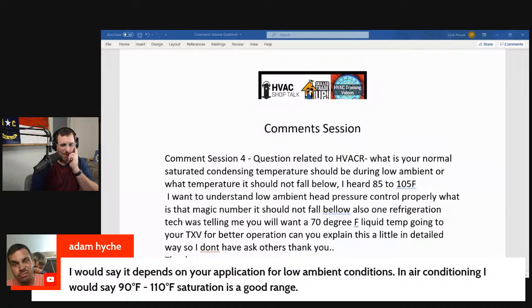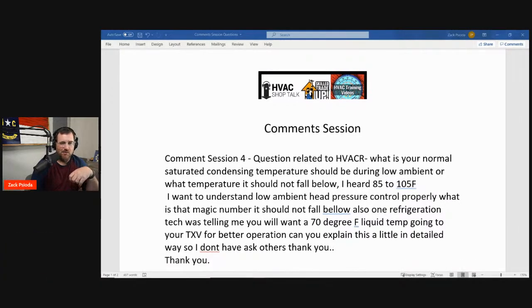I would say it depends on your application. For low ambient conditions and air conditioning, I would say 90 degrees to 110 saturation is a good range. That would put you right in that area we were talking about. So 70 degrees with 20 degrees over ambient will put you at 90 degrees. Maybe that's a good place to start. Like I said, I come from air conditioning, so I'm going to give you air conditioning answers. Okay. So that's where we're at on that one. That's probably the best I can do on that. Hopefully that helps a little bit.